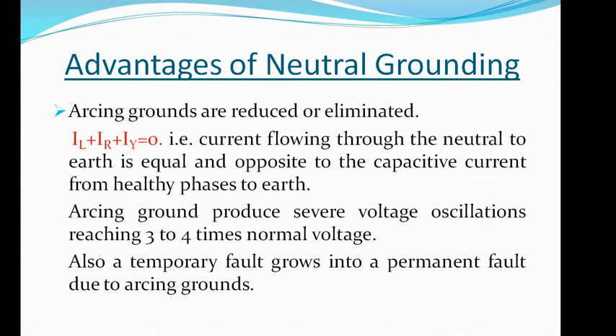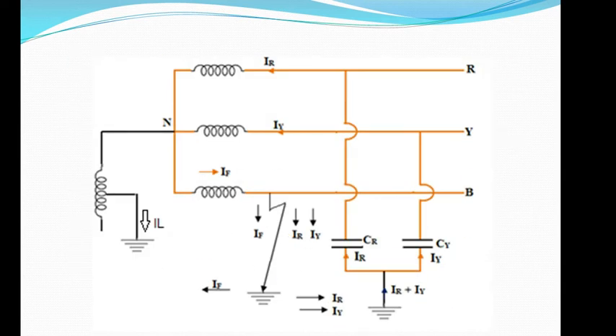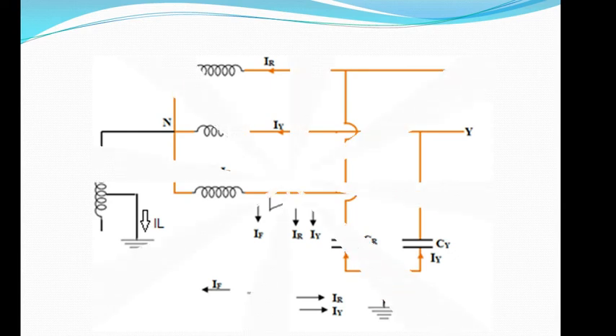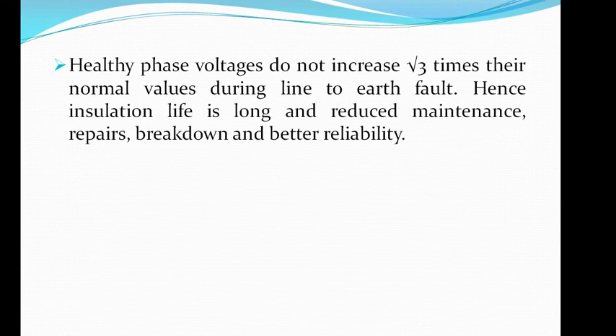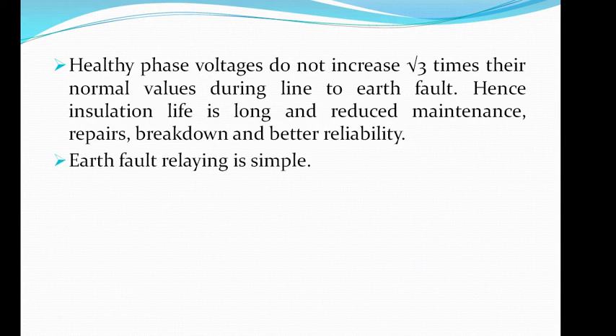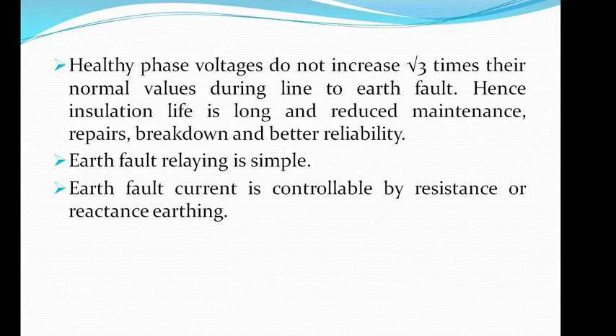Here, a fault has occurred at phase B, so phases R and Y are the healthy phases. The fault current flowing through the neutral path is iL, such that iL + iR + iY = 0, meaning the vector summation equals zero, so the arcing ground phenomenon can be eliminated. Healthy phase voltages do not increase by root three times their normal values during a line-to-earth fault, hence insulation life is longer with reduced maintenance, fewer breakdowns, and better reliability. Earth fault relay design is very simple for a grounded system, and earth fault current is controllable by resistance or reactance earthing.